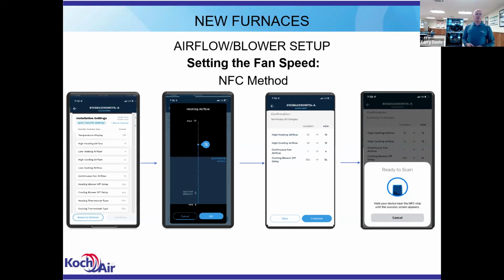Again, on the low cooling airflow, you can set it, or you can let the board set that. And it'll adjust that based on how you set the high cooling airflow. Continuous fan airflow is going to give you that limited range. You can set your heating, cooling, blower off delays. You can tell it on the mid tier, am I using a single stage thermostat or am I using a 2-stage thermostat? If you're using a single stage thermostat, then the adaptive control will determine whether you want to run in low fire, high fire, or low cool, high cool, if you're using a 2-stage outdoor unit.